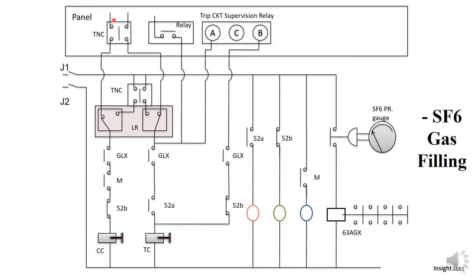The first circuit is our closing circuit. This is CC, which is the closing coil. Here is the GLX contact. If the spring charge contact is made, these two contacts are closed. 52B is the breaker auxiliary switch — if it is closed, then the breaker will operate.